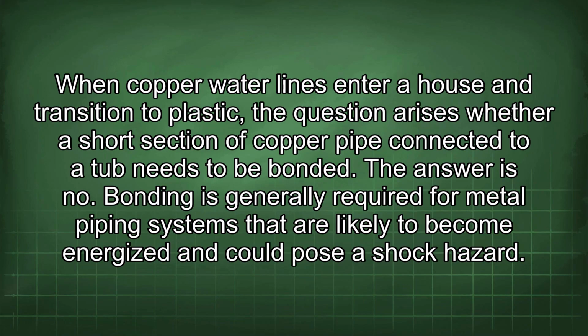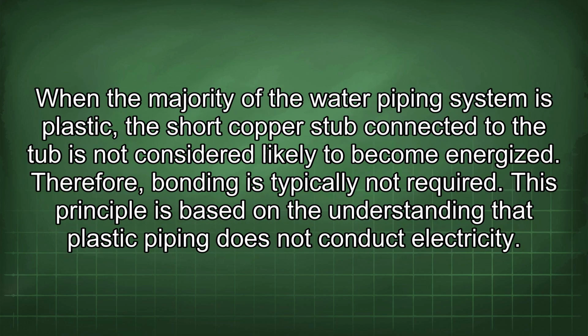When copper water lines enter a house and transition to plastic, the question arises whether a short section of copper pipe connected to a tub needs to be bonded. The answer is no. Bonding is generally required for metal piping systems that are likely to become energized and could pose a shock hazard. When the majority of the water piping system is plastic, the short copper stub connected to the tub is not considered likely to become energized. Therefore, bonding is typically not required.